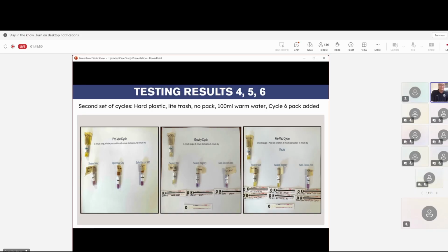But look at your steam strip. Look what it indicates. It says it's okay. It says I reached temperature, but look at your biological. And that could be a problem. And you're going to see the pattern through all of my testing here, and I'm breezing through it. Now for test number 5, I did seal the bag. I did very similar to what everybody does. I tie wrapped it and left a little bit of a hole so that there's about a half-inch vent hole in the top of the bag, and then I threw it in. And then the Safe-Decon one, the BioPro 300 went.